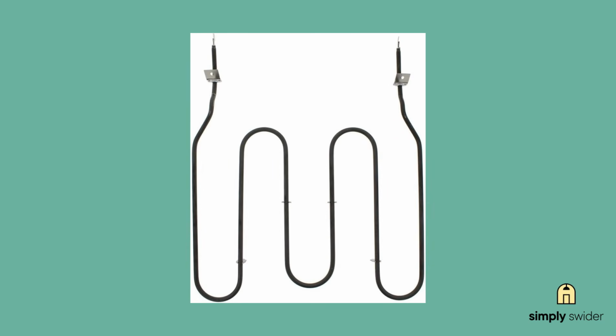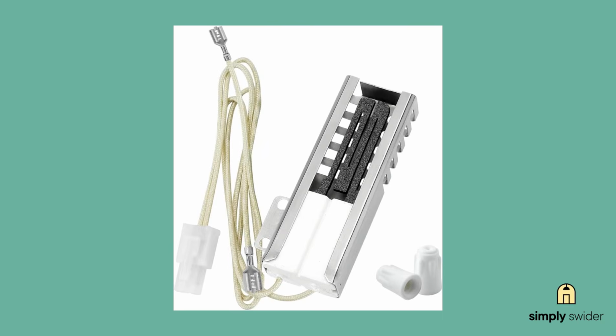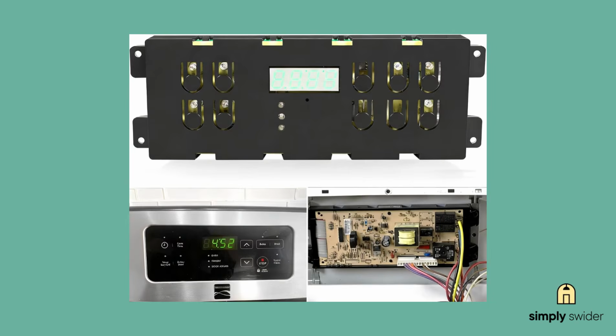Here's what each part actually does and how to test it properly. The bake element converts electricity to heat through resistance. Test it with a multimeter for 0 to 50 ohms. The gas igniter needs to draw enough current to operate the safety valve. You need a clamp-on amp meter to verify 3 plus amps. Control boards often manage most of the logic and power distribution. Test for proper voltage output during a call for heat, depending on the system.